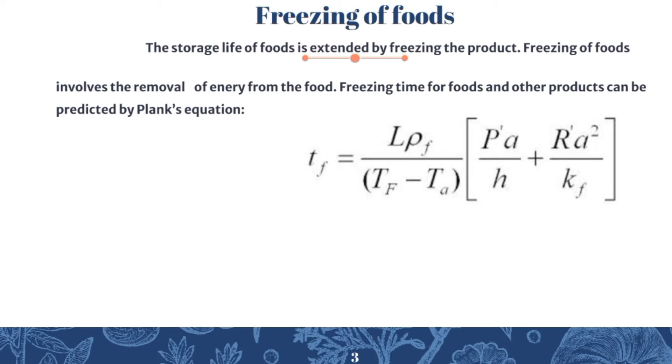Freezing time for foods and other products can be predicted by Plank's equation. In Plank's equation, small tf is the freezing time in seconds, capital Tf is the freezing temperature of the food product, Ta is the temperature of cooling medium, a is the thickness of slab or diameter of cylinder or sphere, k is thermal conductivity, and lambda or L is latent heat of freezing.